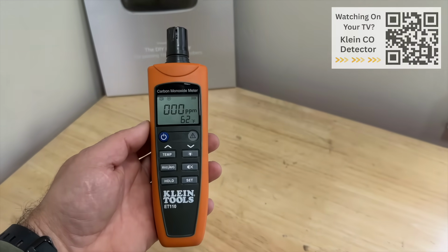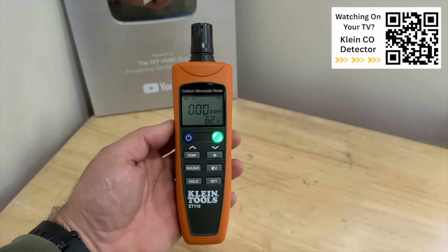Now, two critical things that I want to mention are a carbon monoxide detector, and you can even get this with smoke and carbon monoxide, and then a handheld carbon monoxide detector. This will tell you without any uncertainty, and both of these really will, but this is a handheld device that we can put up to something and it will immediately tell you if there's carbon monoxide and how many parts per million. So I want to demonstrate this real quick, as well as show you some features of this X-Sense carbon monoxide detector. So this is a Klein ET110 carbon monoxide detector, and this is about $120.